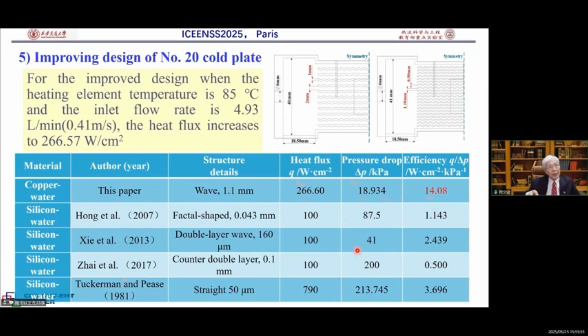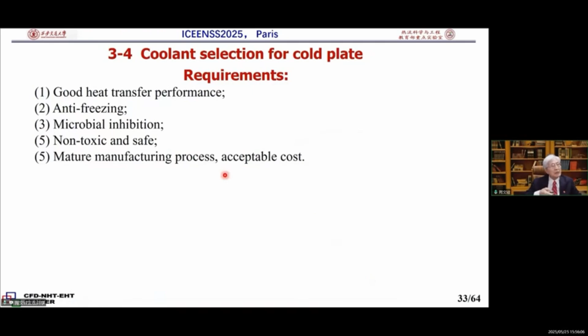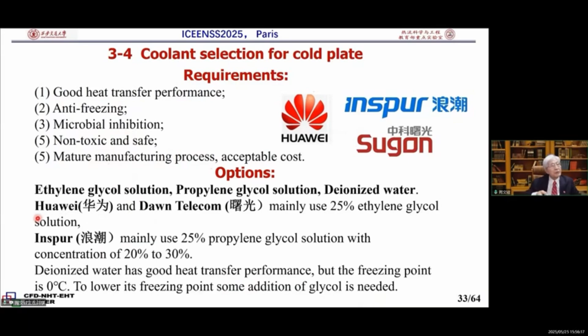And the ratio of q over delta P is 14, compared to Tuckerman and Pease in 1981, where it's only about 3.6. The second problem is the coolant selection for the cold plate. It should meet several conditions, such as heat transfer, anti-freezing, non-toxic, and so on. Now, in China, the three big companies, Huawei, Inspur, use ethylene glycol or propylene glycol.